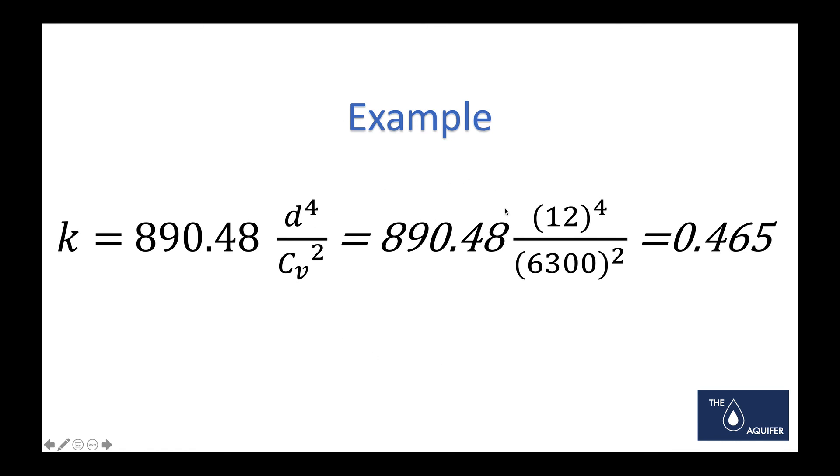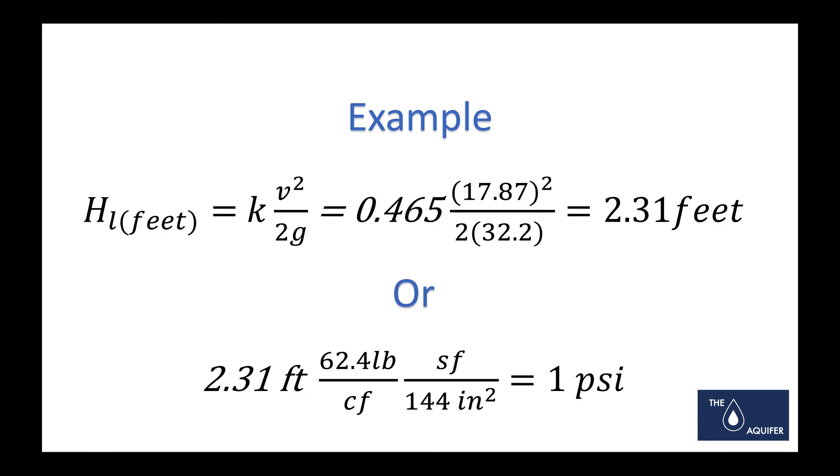Applying those numbers, we've got our diameter—12 to the fourth power—divided by our Cv to the squared power. We come up with a K value of 0.465. That seems reasonable based on the type of work and our knowledge of those numbers. Then applying that through Darcy-Weisbach: 0.465 times our velocity squared divided by 2 and our gravity constant, we would come up with our head loss in feet is 2.31 feet.